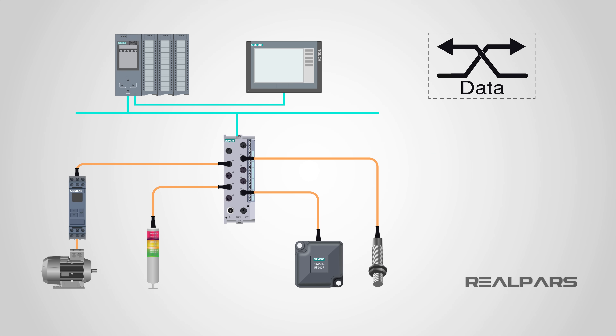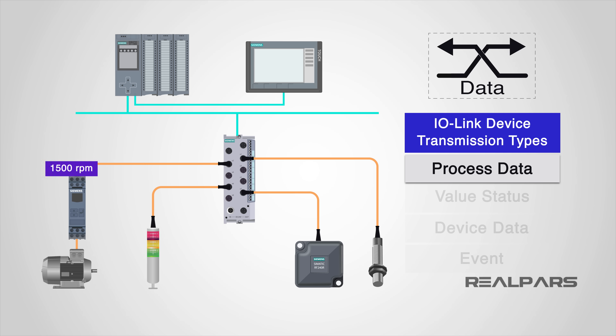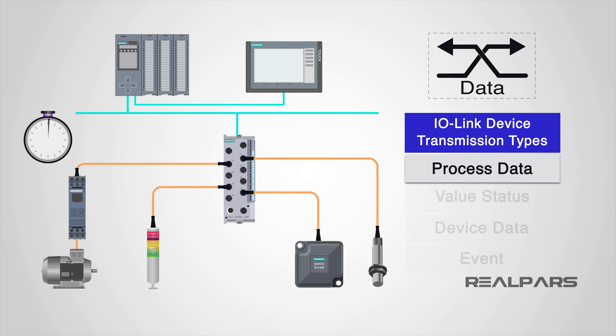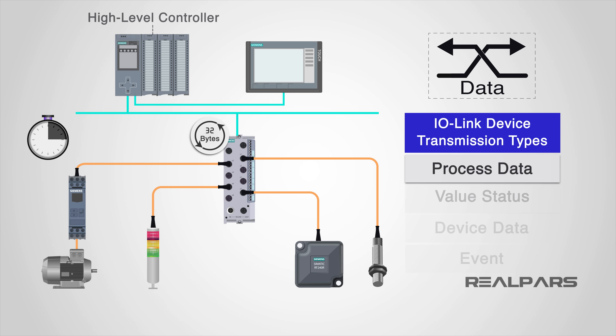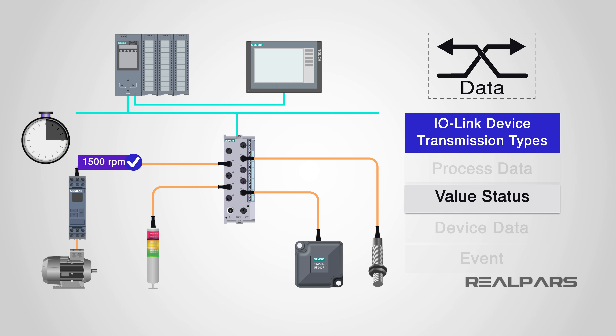An IO-Link device has four types of transmission: process data, value status, device data, and events. The process data is considered as the latest state of the sensor or actuator, such as speed. Process data is transmitted cyclically, which means automatically at regular defined intervals. Up to 32 bytes of process data can be processed, and it is defined by the high-level controller. The value status indicates whether the process data is valid or invalid and is transmitted along with the process data cyclically.